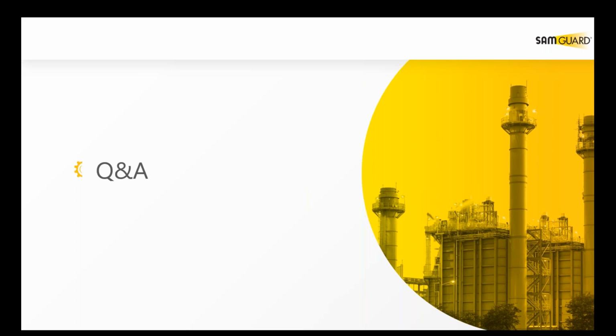We see problems with valves, and we see problems with pumps, and with catalyst and with heat exchangers. And you sometimes can identify blockage in the heat exchanger, not by the behavior of the heat exchanger, but because of the behavior of the valve before the heat exchanger, which suddenly changed its behavior because of the blockage.